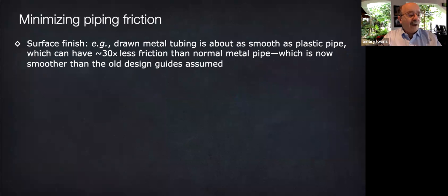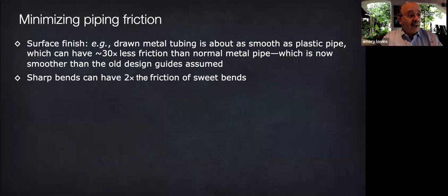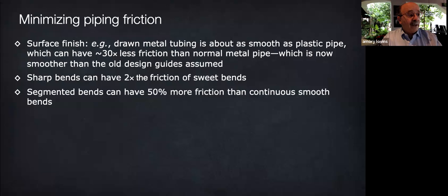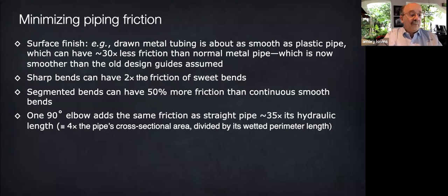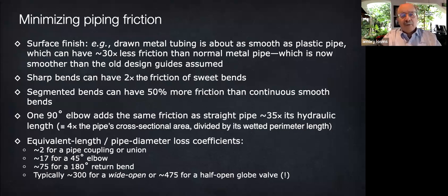The surface finish matters, and the old design guides, specification tables, may not take that into account. Sharp bends can have double the friction of gradual, so-called sweep bends. Segmented bends, where they bend a piece at a time, can have again as much friction as continuous smooth bends. 90-degree elbows have a huge amount of friction, and you can look at loss coefficients that show that anything that disturbs the flow is introducing friction, probably about the worst being a globe valve.